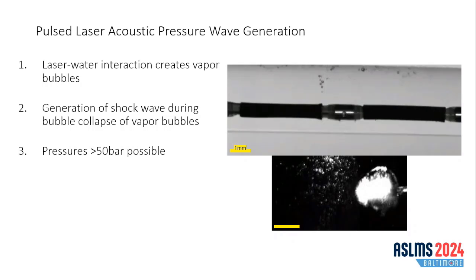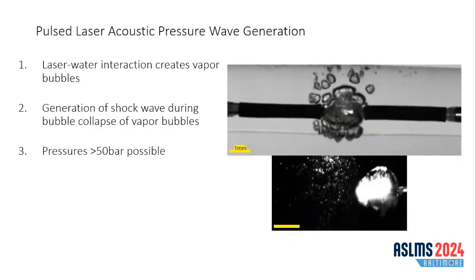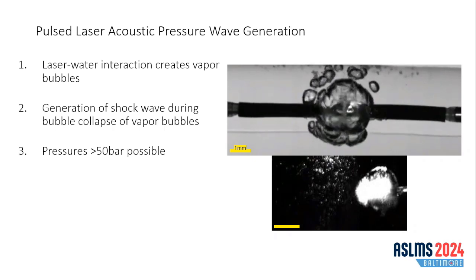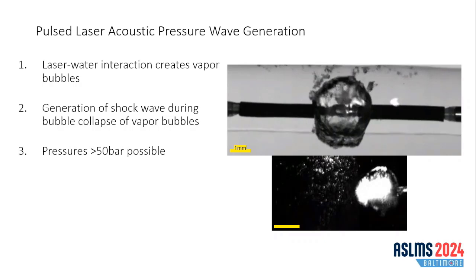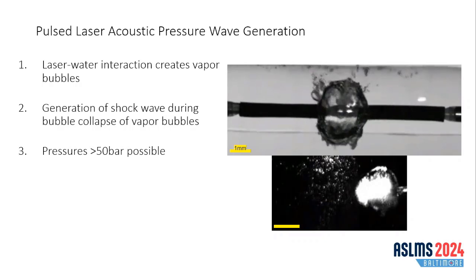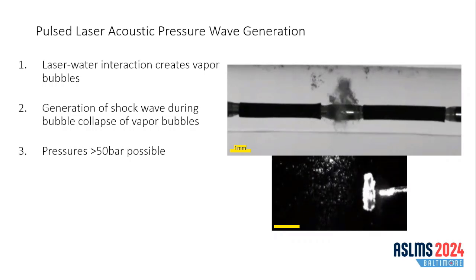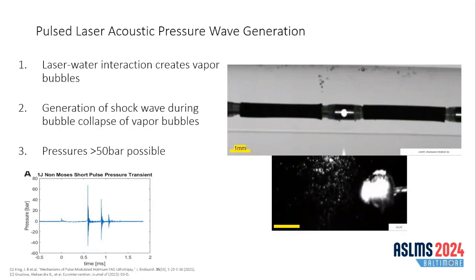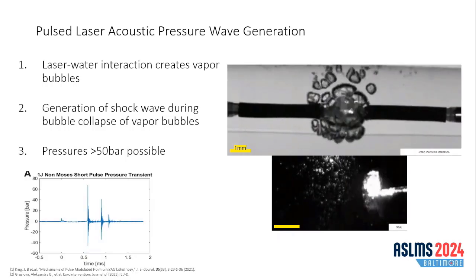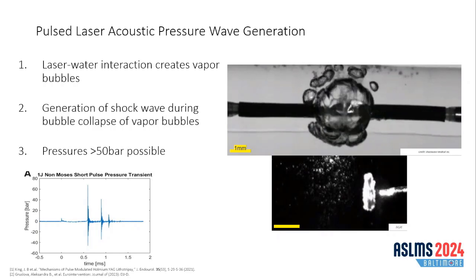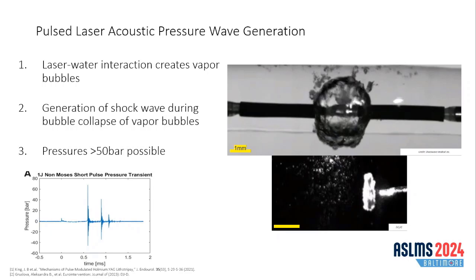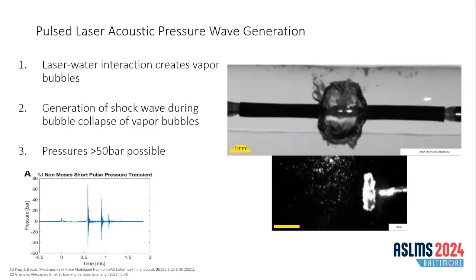We show the two cases. One is the spark electric discharge lithotripsy. You can see here there's an initial spark in the beginning causing a vapor bubble to expand, and then a collapse of which sends a shock wave. Similar to that, the laser approach also is able to provide a similar sort of mechanism, generating shock waves as well as generating strong enough pressure waves at the collapse of the vapor bubble. As you can see here, in a smaller form factor, because the fiber here is only 200 microns compared to about a millimeter in the shockwave case.